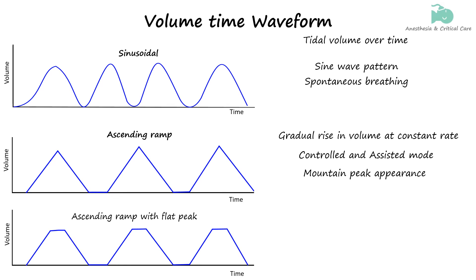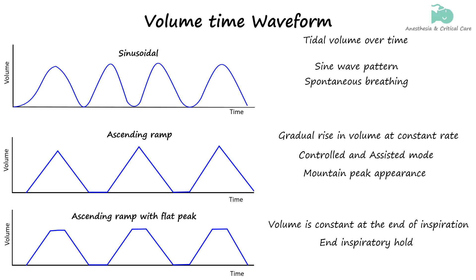The ascending ramp waveform may also have a plateau or flattened area at the peak. During this flat or plateau phase, the volume remains constant, indicating that the lungs have received the full breath and no more air is being added. This happens at the end of the inspiratory phase, often during an inspiratory pause maneuver.